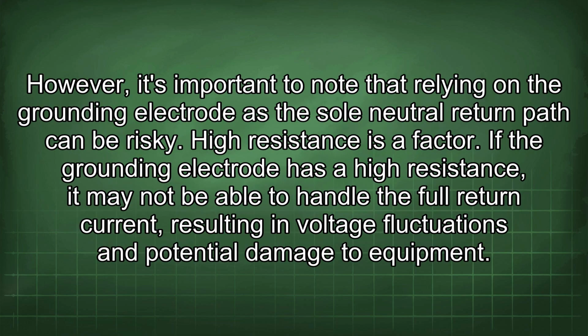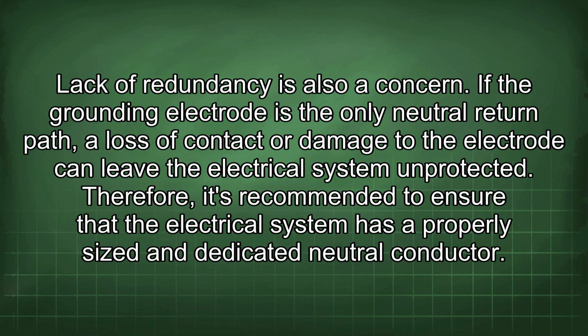However, it's important to note that relying on the grounding electrode as the sole neutral return path can be risky. High resistance is a factor. If the grounding electrode has a high resistance, it may not be able to handle the full return current, resulting in voltage fluctuations and potential damage to equipment. Lack of redundancy is also a concern. If the grounding electrode is the only neutral return path, a loss of contact or damage to the electrode can leave the electrical system unprotected.